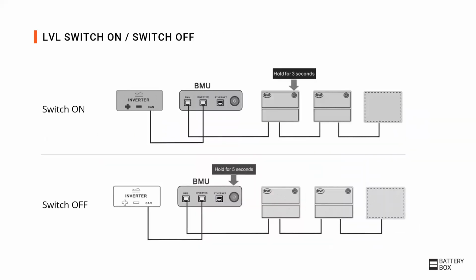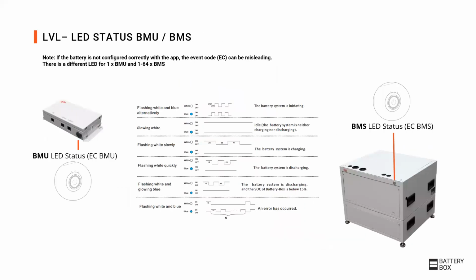Once the cabling is done, the system can be switched on by pressing the LED button on the LVL for 3 seconds. To turn the system off, the LED button on the BMU has to be pressed for 5 seconds. Then all LVL should turn off. When the battery is on, the LEDs on the BMU and on the individual LVL will show a status similar to the HVS-HVM product. While the BMU shows the general system status, the single LVL show their individual BMS status. Please refer again to the manual and the service guideline for the exact meaning of the different blinking status.